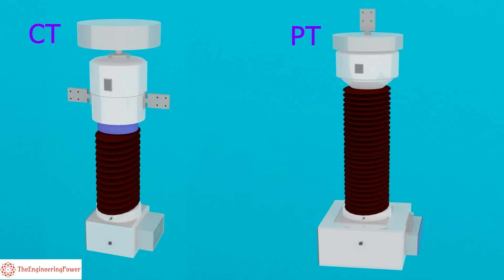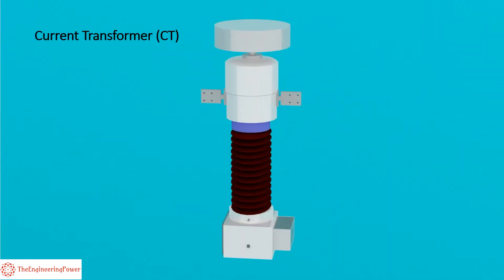The structures of a CT and PT in a substation are quite similar. Here is how to differentiate between a CT and a PT. As a CT is always connected in series with the power line, therefore it has two primary terminals that are clearly visible on both sides.